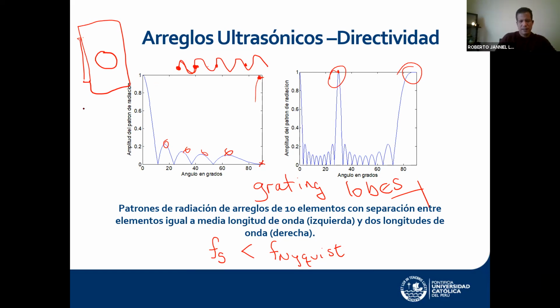What happens is that when I turn my transducer on, there would be the main lobe in here, right? But there is also, let's say, a grating lobe in here. And actually, very likely I will have the grating lobe in here too, because it's symmetric anyway. So in principle, when I receive echoes from here, I should receive nothing, because there are no reflectors. The main beam of the transducer is pointing in that direction, and there is no reflection coming back.